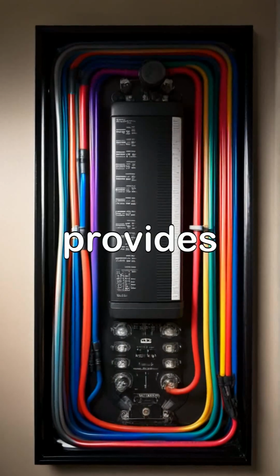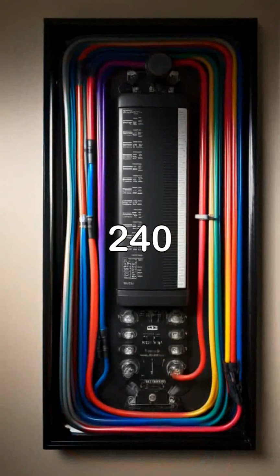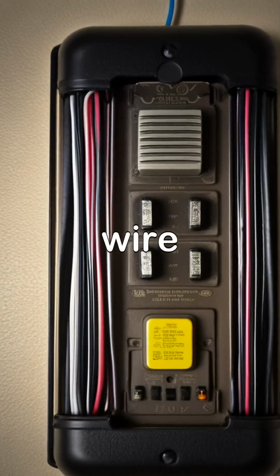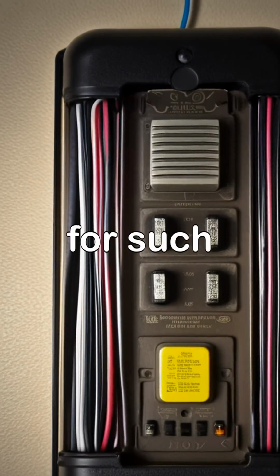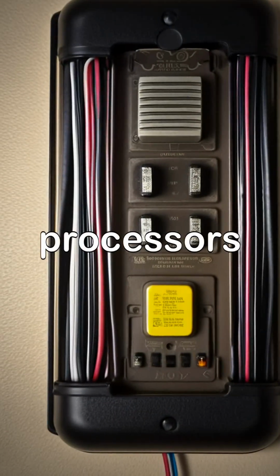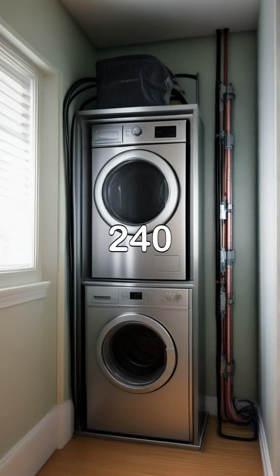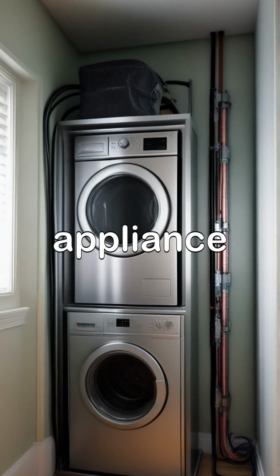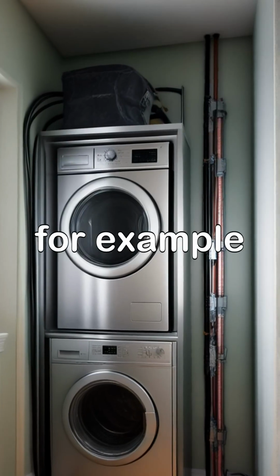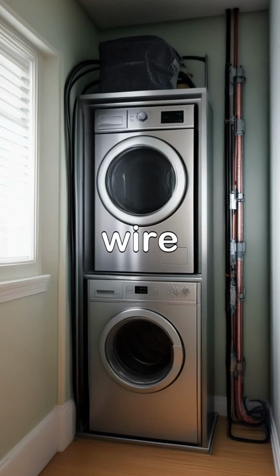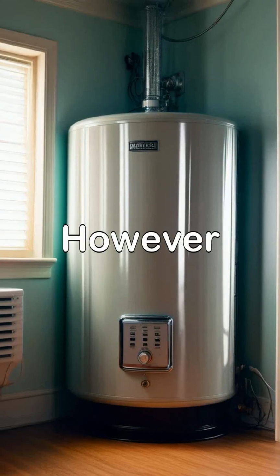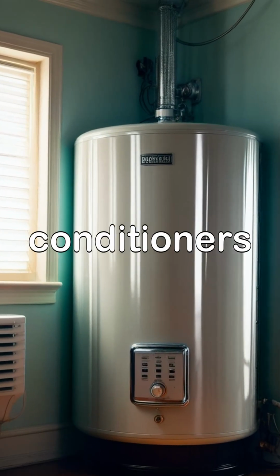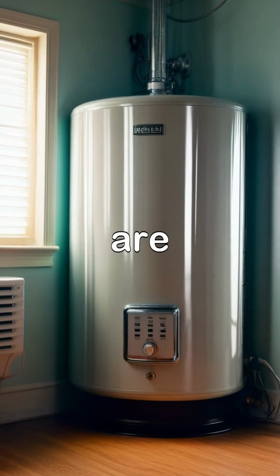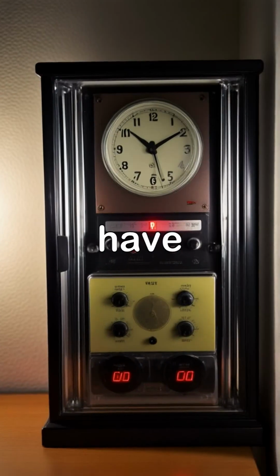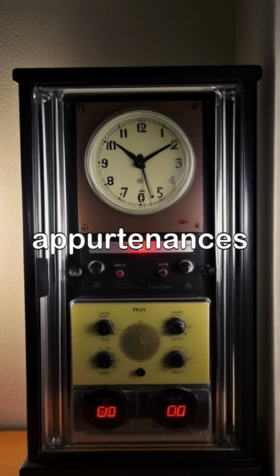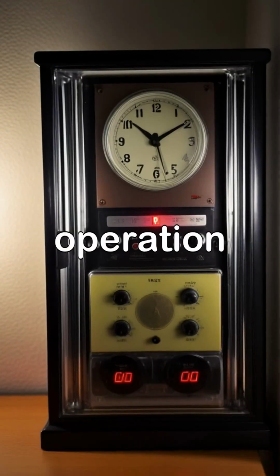The three-wire system provides a home with both 120 volt and 240 volt. The neutral wire and either hot wire combine to supply 120 volts for such items as lamps, radios, food processors, and wall receptacles. When 240 volt service is necessary to operate a major appliance such as a range or clothes dryer, for example, both hot wires combine with the neutral wire to supply the required electricity. However, note that water heaters and large air conditioners also require 240 volts, but they are connected only to hot wires. They don't have clocks, timers, lights, or other appurtenances that require 120 volts for their operation.